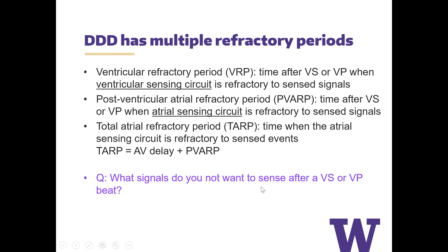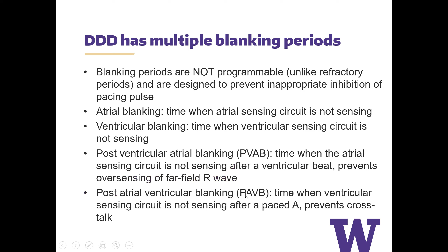Blanking periods, unlike refractory periods, are not programmable. And several of these blanking periods, again, I don't have the time to really go into detail here, but the bottom line of programming the refractory periods and then changing the lower rate limit, excuse me, and the upper rate limit to see what you get in terms of the blanking periods is again to avoid over and under sensing.